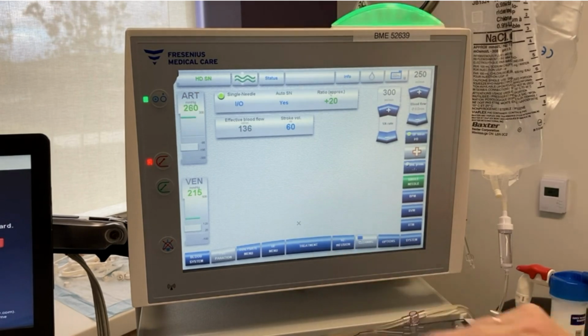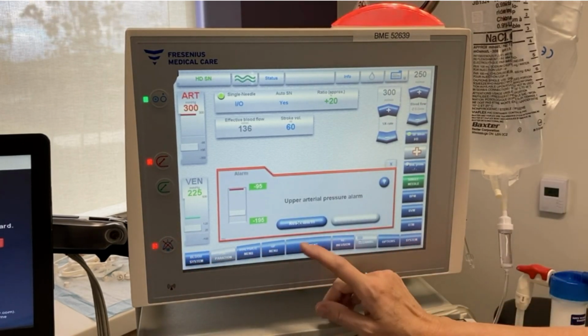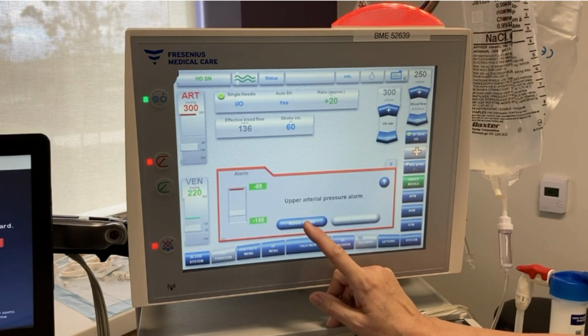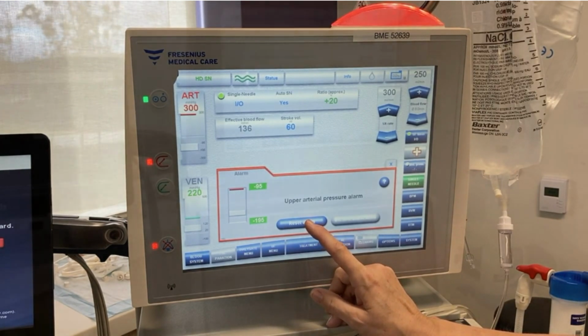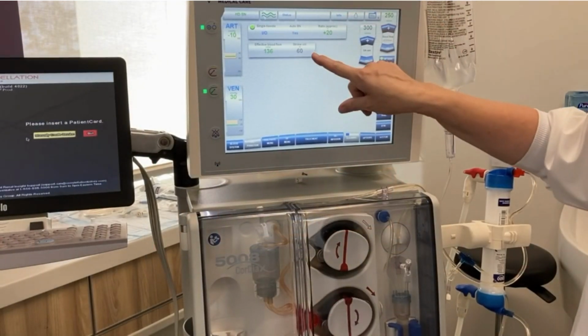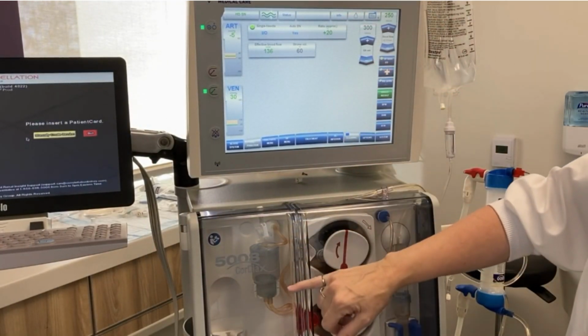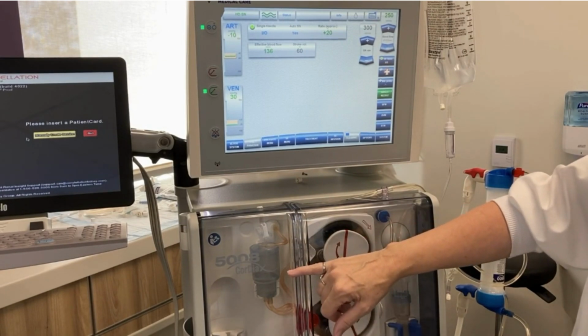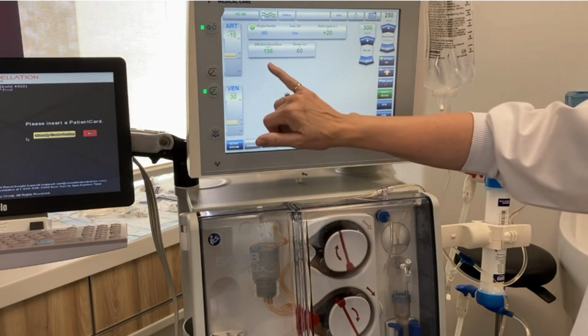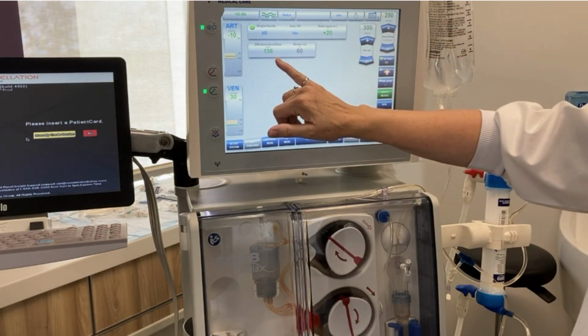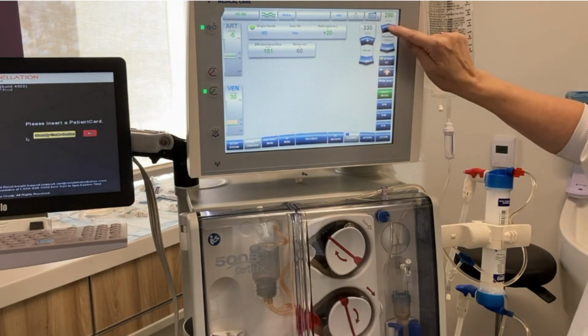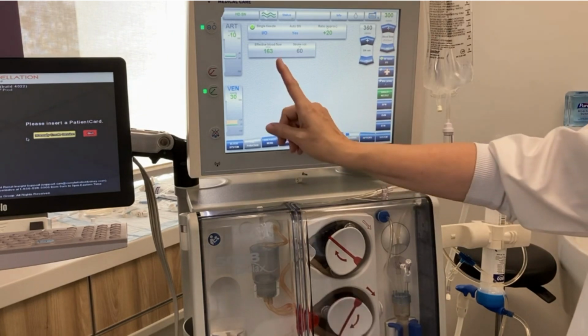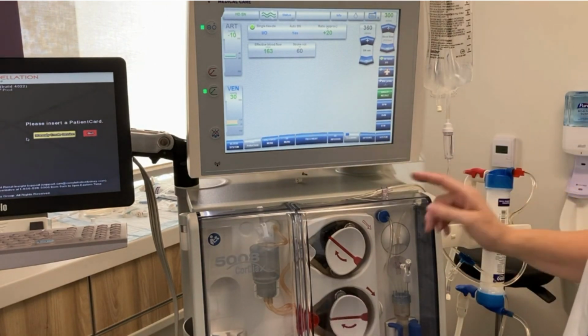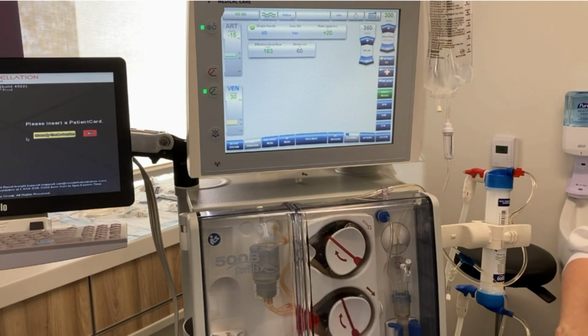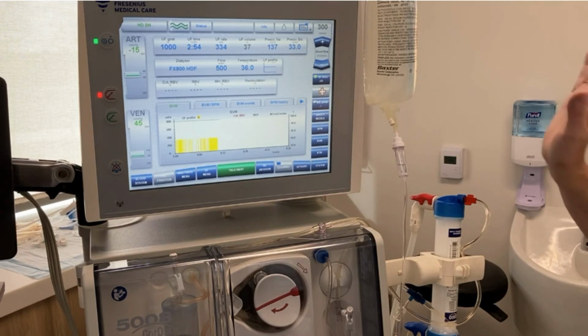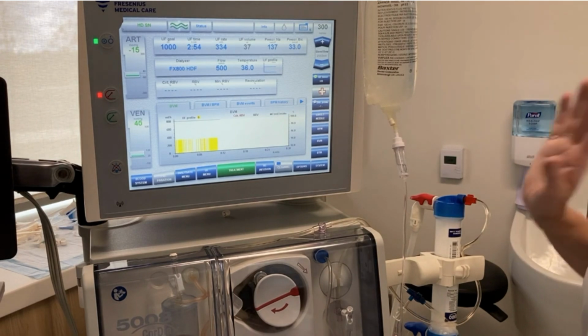So it keeps alarming because we don't have an actual patient running right now. We're just running a simulation, so the pressures are not exact. Okay, so here we're showing our stroke volume as 60, and the stroke volume is the volume that is in the arterial chamber. It's now 250, so that makes the effective blood flow only 136. When I turn up our pump speed, it's going to increase my effective blood flow. And our goal is to have the highest possible effective blood flow. Okay, so that's everything for your single needle setup and for running your single needle.